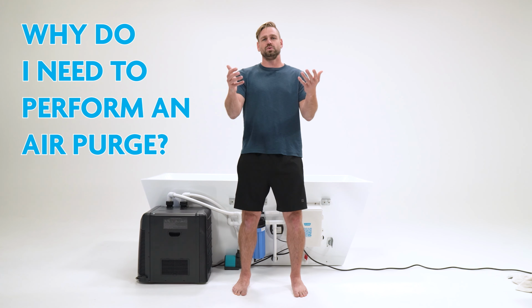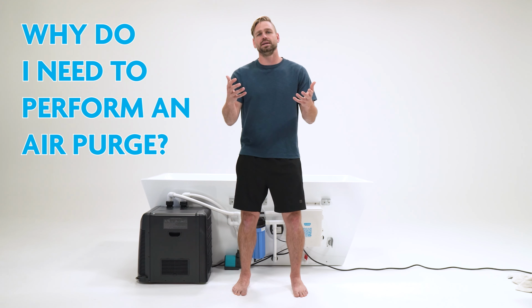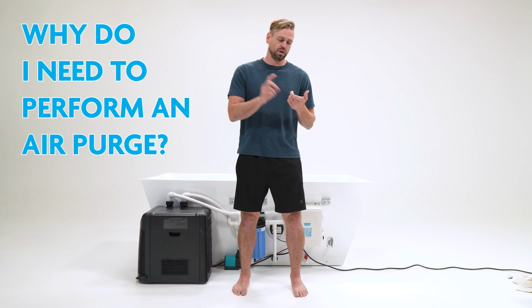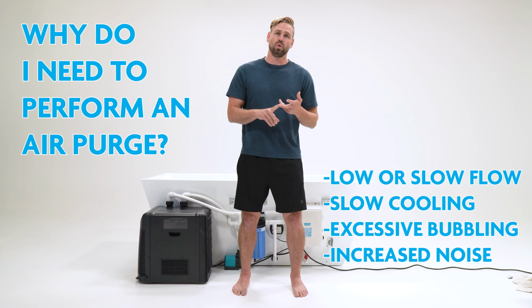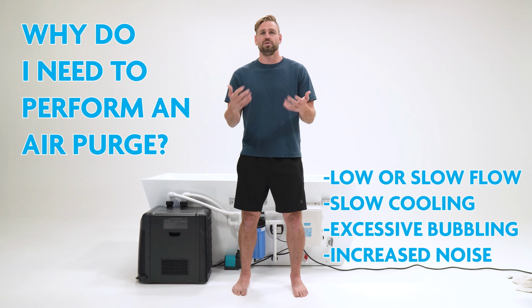We're gonna show you how to perform an air purge, and you might be asking, why do I need to perform an air purge? Air can get into the system, which can cause low flow, no flow, or excessive bubbling with increased noise. So what we need to do is flush this air out of the system. Most of the time this can be caused by filling the plunge and having the out connection on the chiller connected, which traps that air in there.